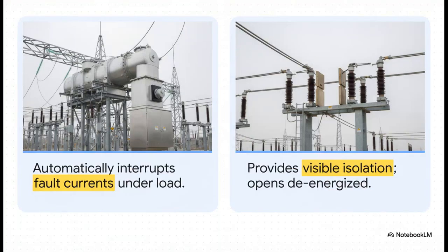Now there's a critical difference between the circuit breaker we just saw and component 6, the isolator, sometimes called a disconnector. While the circuit breaker is designed to blast open automatically while massive power is actively flowing, the isolator is strictly a manual safety device. It provides a physical, visible break in the circuit so maintenance crews know for an absolute fact that the line is safe to touch.